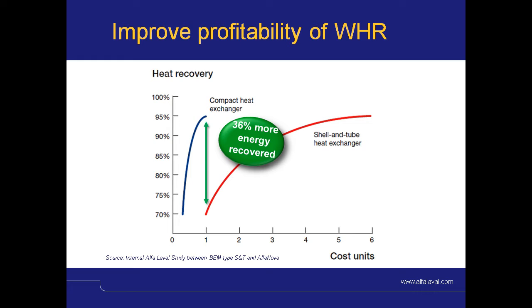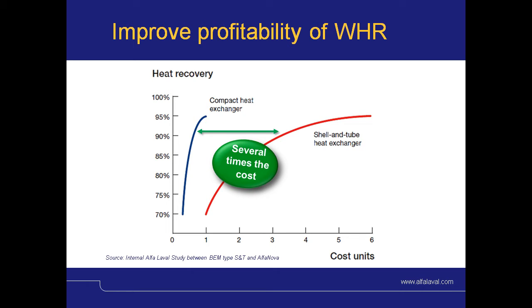This graph compares an interchanger or a preheater using shell and tubes or a compact heat exchanger. Plants often stop at 70% of heat recovery in preheaters or interchangers. Doing more is not profitable for shell and tubes, but compact heat exchangers can, at similar cost, achieve much more. This means that in many plants there is up to 36% more energy to be saved by just switching heat exchangers. And to those plants who consider to improve waste heat recovery, I strongly recommend to take compact heat exchangers into the equation.